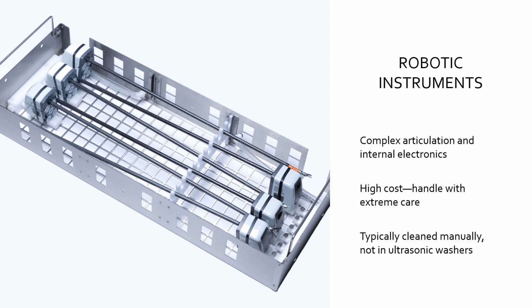Me personally, I'm going to send them through the washer disinfector. We do have a rack especially for robotic instruments. You hook it up to the port, so as it's washing, it's flushing, it's putting chemicals and water and rinse water and all that through that port to clean it. So I go a step further, and I do put it through the washer disinfector, just as a special precaution on my part.